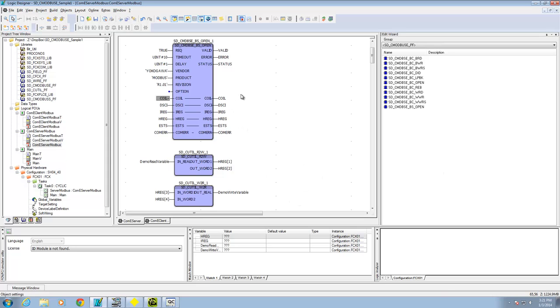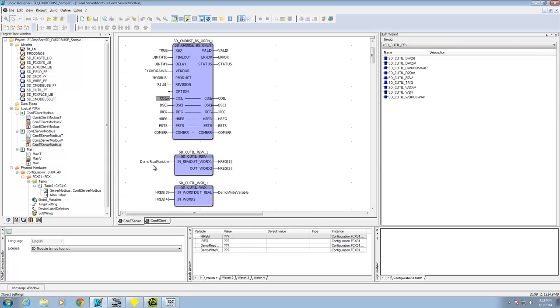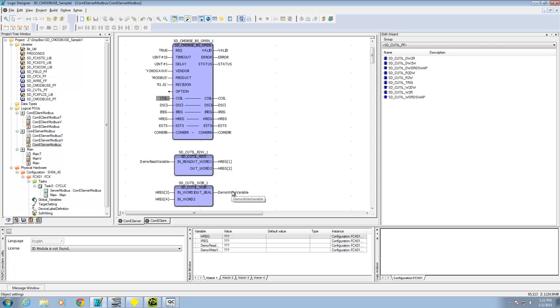To populate those arrays, I've used a couple of blocks that can take a real variable and put it into two words. The variable type I put them into is the hreg, the holding register. I put values into the first part of the array and the second part. Down here I'm doing the reverse — taking holding registers and converting them back into a real value. The demo read variable would be something I want to read on my HMI, like a process variable. The demo write variable is something like a set point that I want to write from the HMI into the Stardom unit.